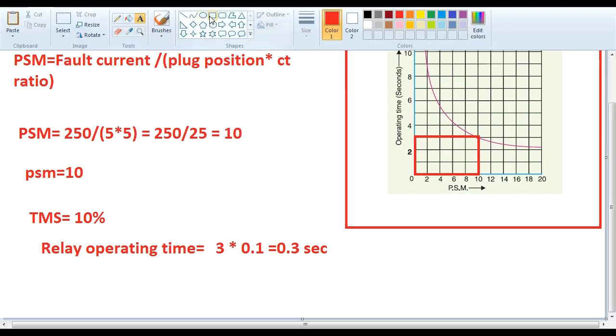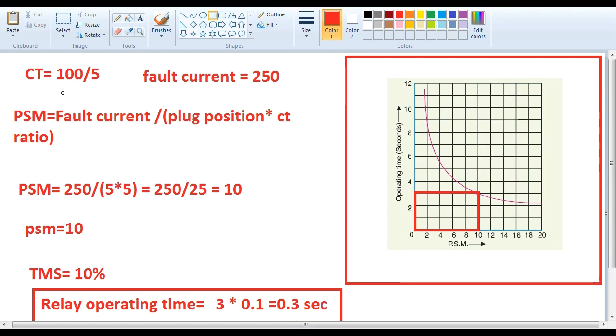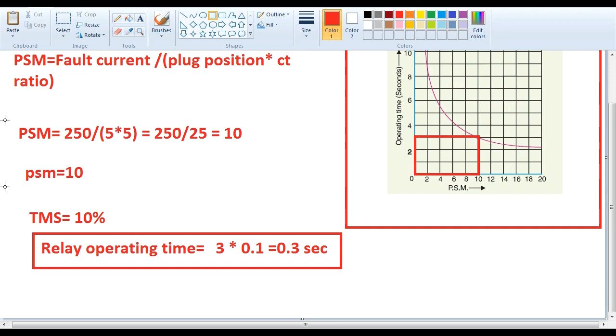Let's see the relay operating time. You can adjust the TMS. The PSM is also adjustable. There is a plug position and other overcurrent settings. We can use the overcurrent and earth fault. The difference is: for overcurrent you use a CT of 100/5, and if it is 1000/5 it is still overcurrent. We can use the PSM and TMS for earth fault as well. If you like this video, please share it and subscribe. Bye bye.